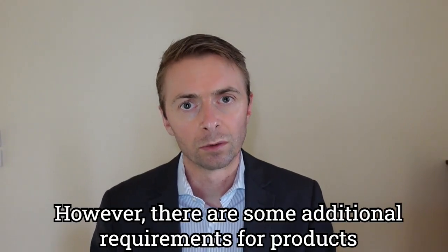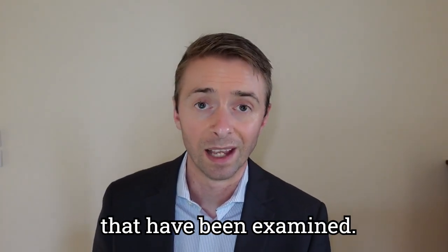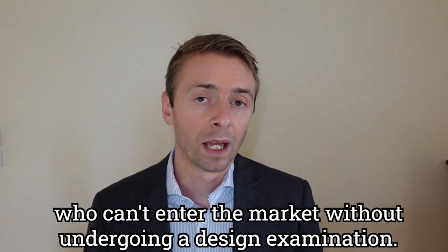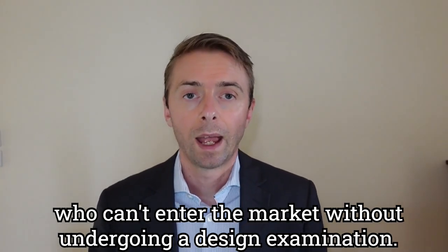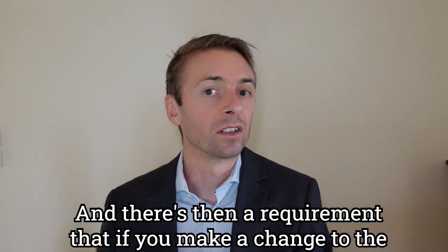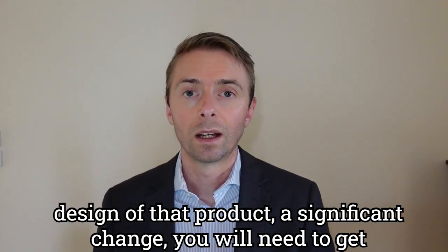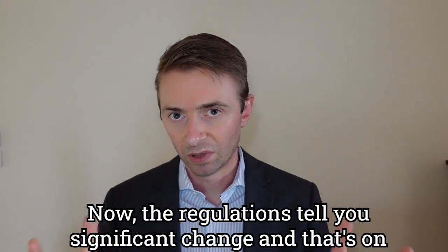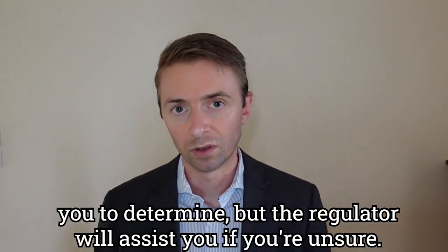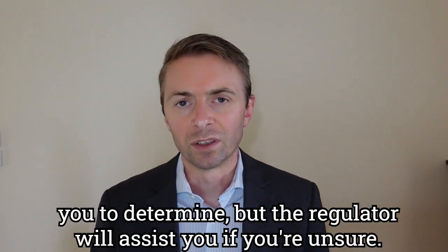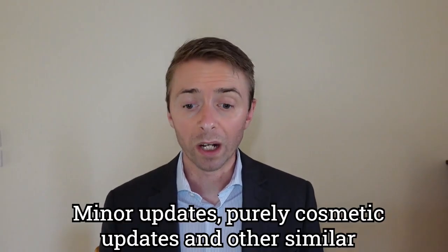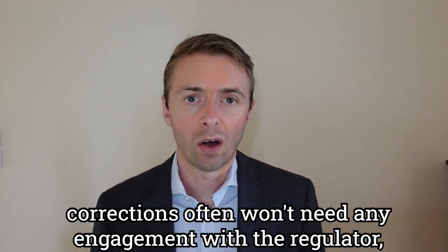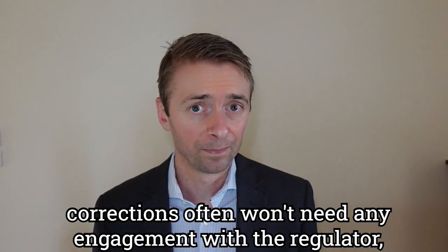However, there are some additional requirements for products that have been examined, which I mentioned before. So in Australia, that's Class 3 products, which can't enter the market without undergoing a design examination. And there's then a requirement that if you make a significant change to the design of that product, you will need to get that assessed by the regulator. Now, the regulations tell you significant change, and that's on you to determine, but the regulator will assist you if you're unsure. Minor updates, purely cosmetic updates, and other similar corrections often won't need any engagement with the regulator.